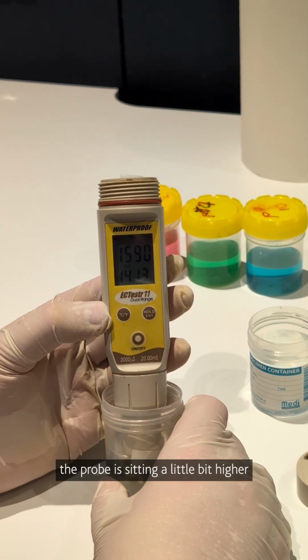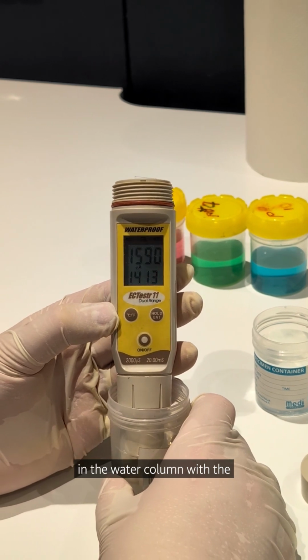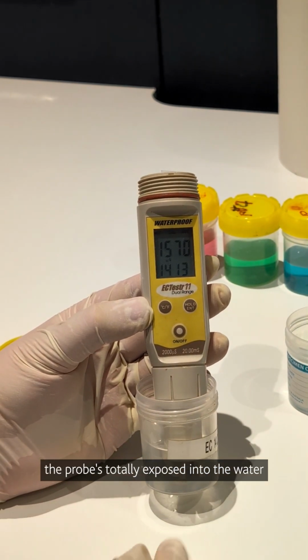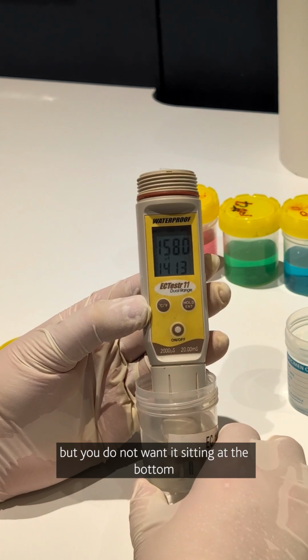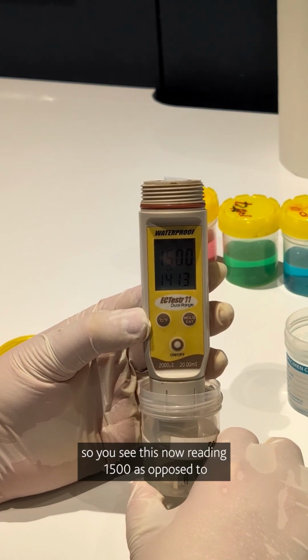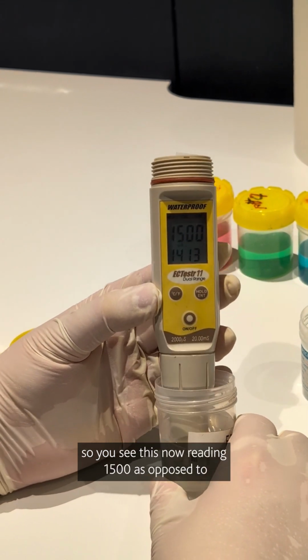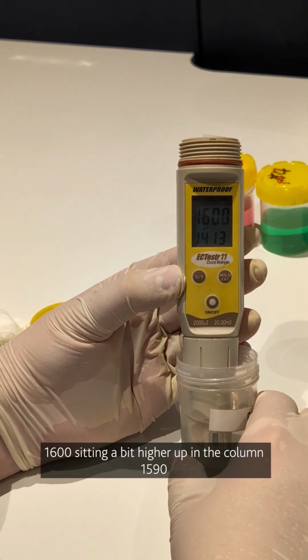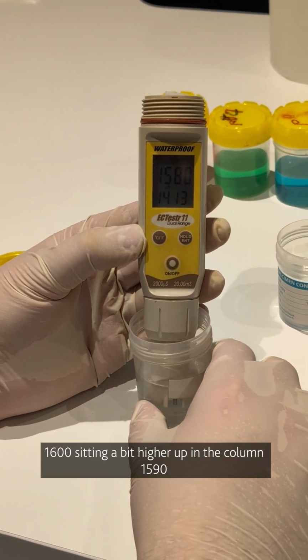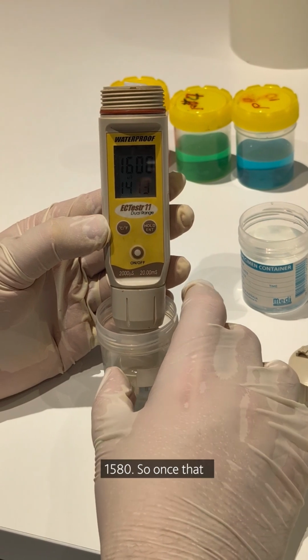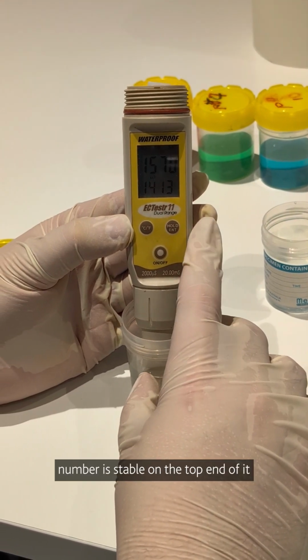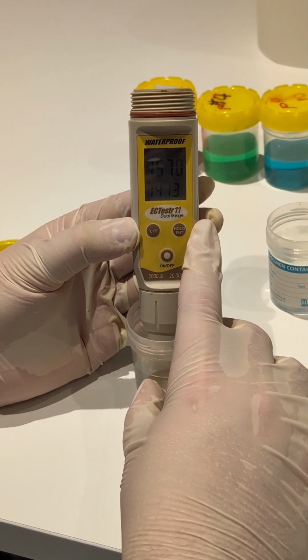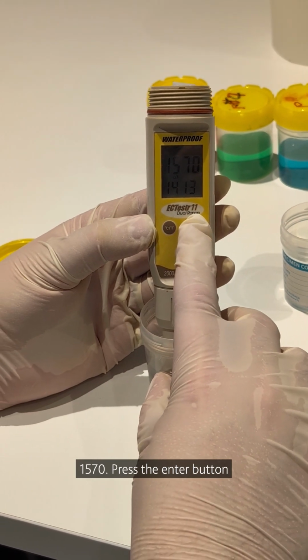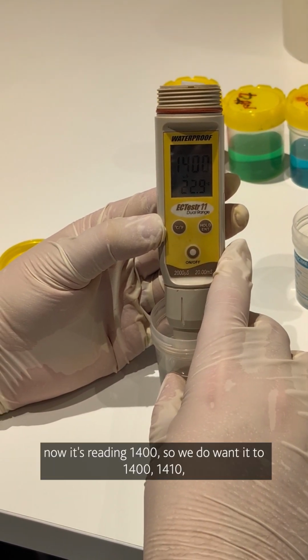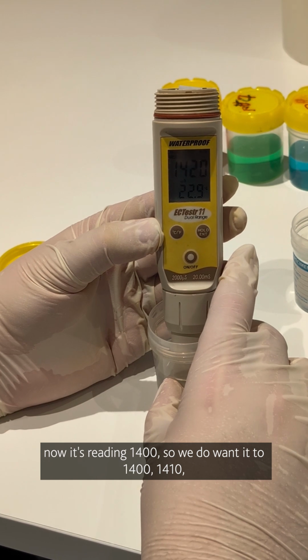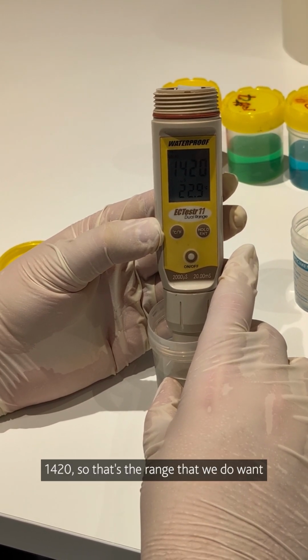You do want to make sure that the probe is sitting a little bit higher in the water column, with the probes totally exposed to the water, not out of the water, but you do not want it sitting at the bottom because you may get a slightly different number. So you can see that's now reading 1500 as opposed to 1600 sitting a bit higher up in the column, 1590, 1580. So once that number is stable on the top end of it, 1570, press the enter button. Now it's reading 1400. So we do want 1400, 1410, 1420. So that's the range that we do want.